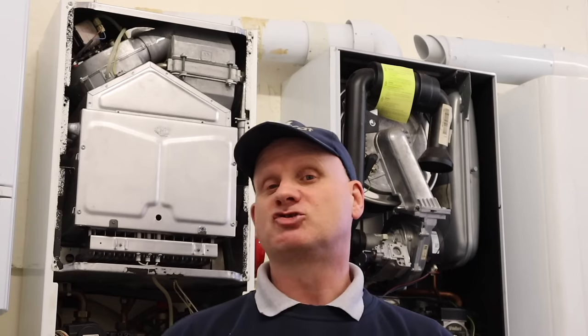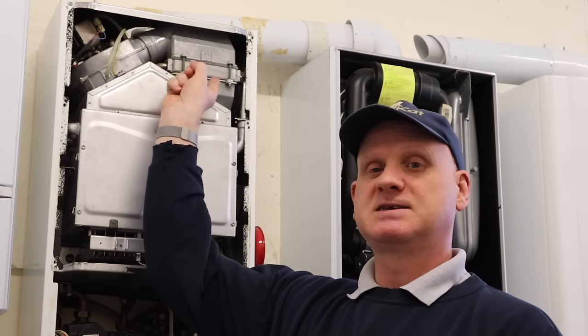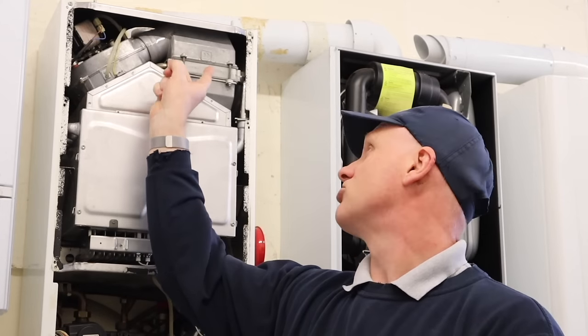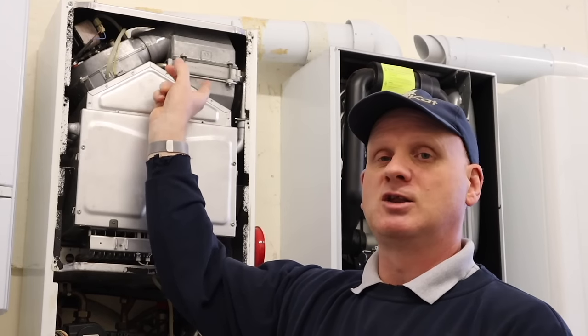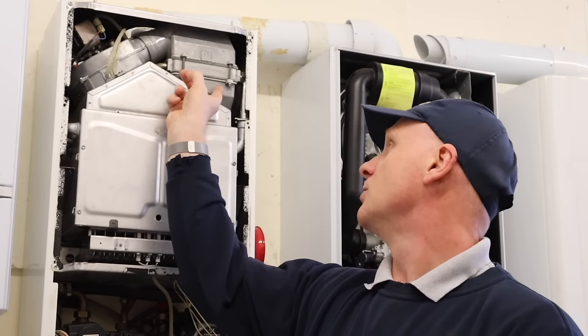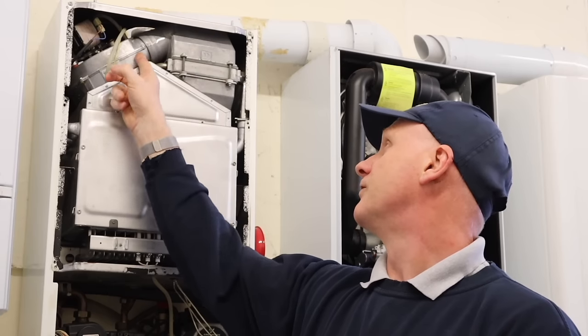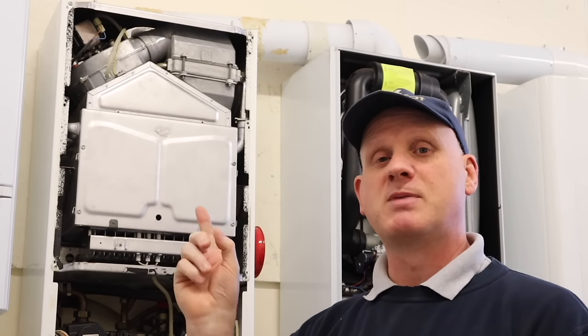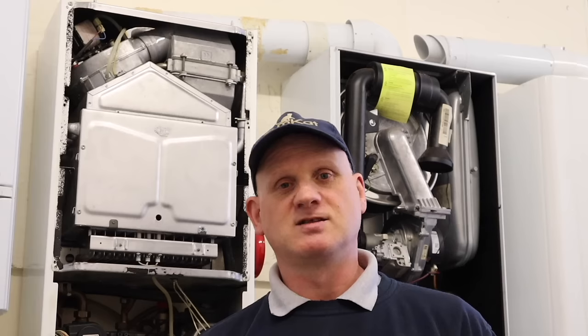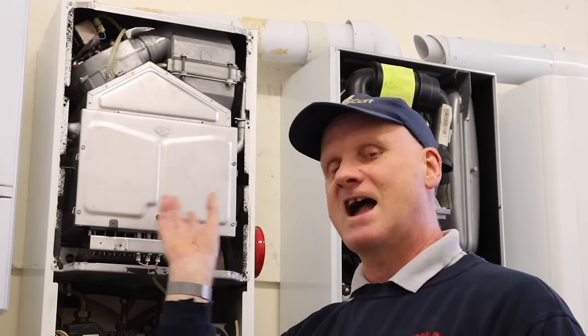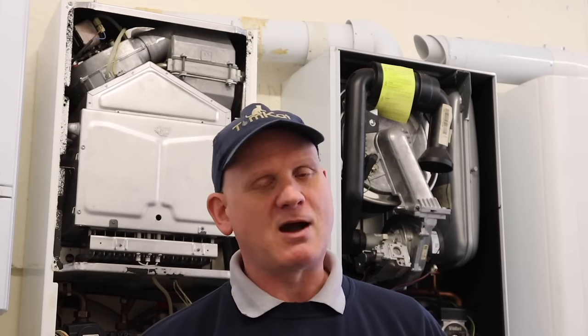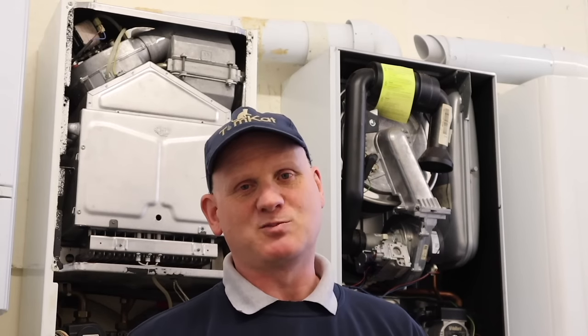And what they did to try and make them condensing was add a secondary heat exchanger here. This is where the boiler would condense in here. So the return water would come to here. The flue then would preheat the water coming back in, so it would only condense in central heating mode. So this is an atmospheric burner, which was only about, at its best, 89% efficient.